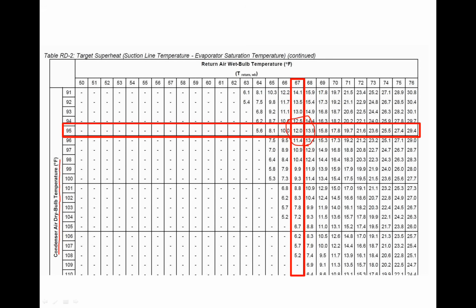But you can see as those load conditions change, right, as the wet bulb temperature goes up from 68, 69, 70, well, that target superheat goes to 13.8, 15.8, 17.8, 19.8. It increases also. And you can see as the outdoor air temperature goes up, the target superheat goes down. And we'll look at these relationships in more detail here in a second.